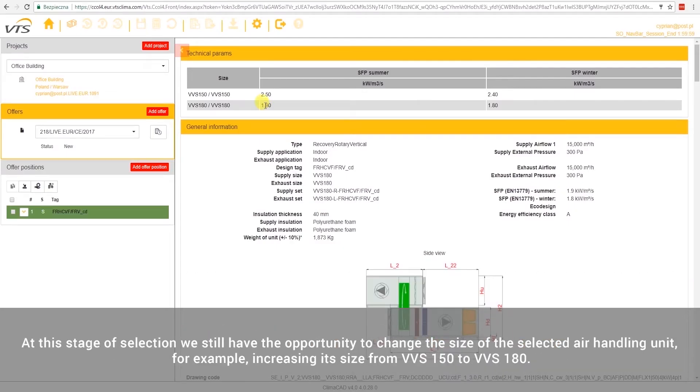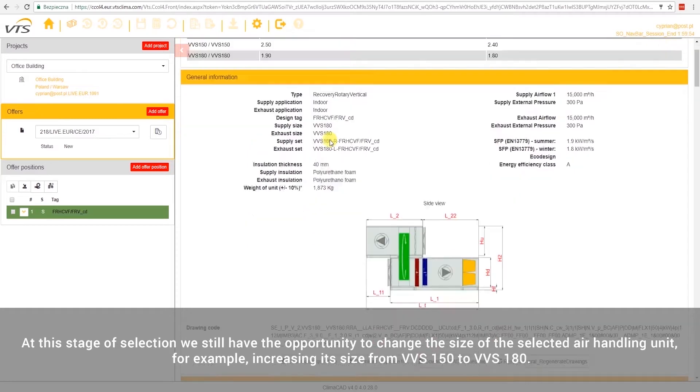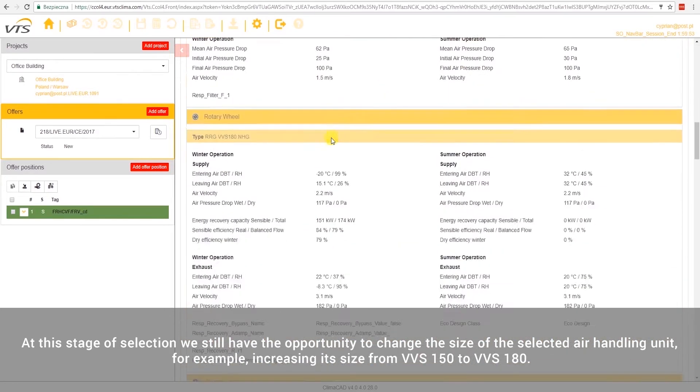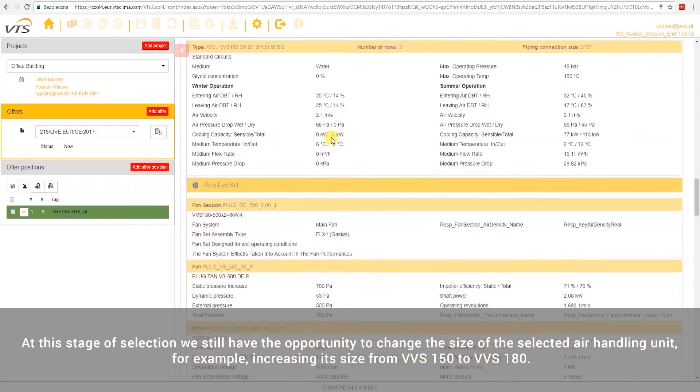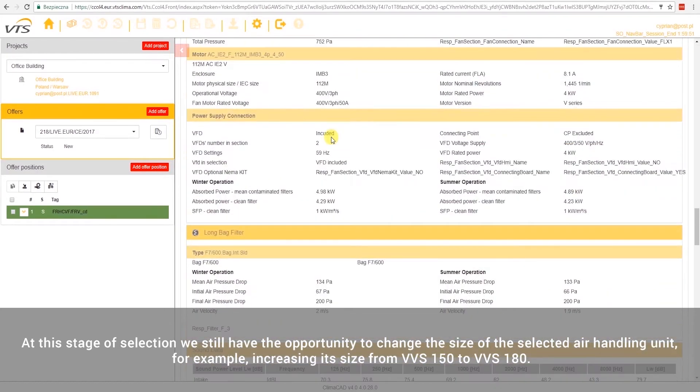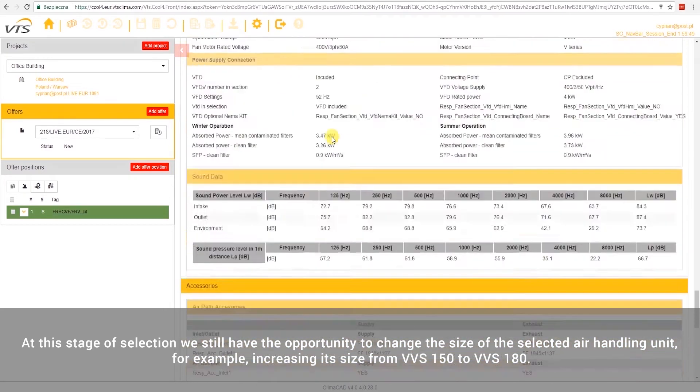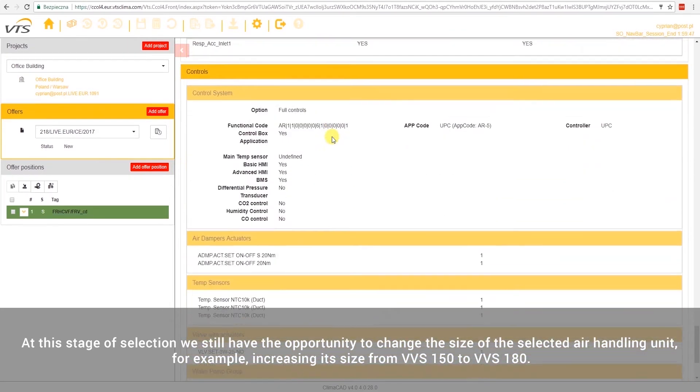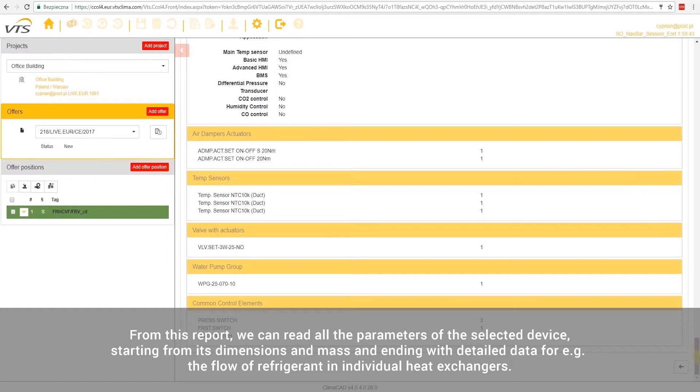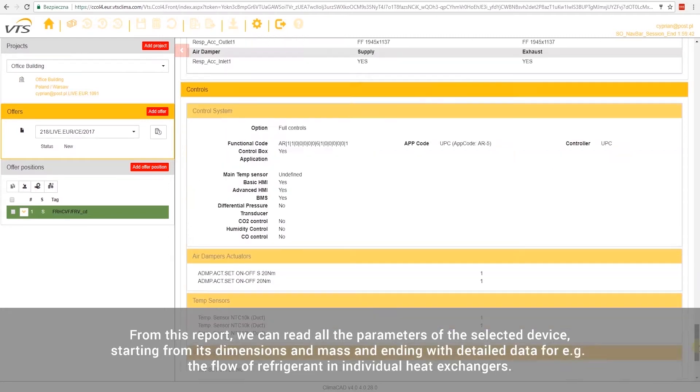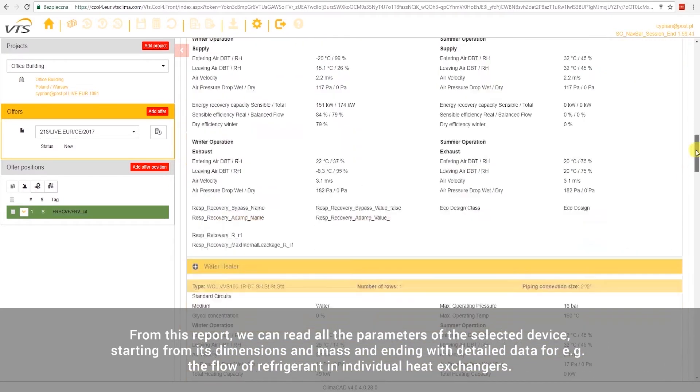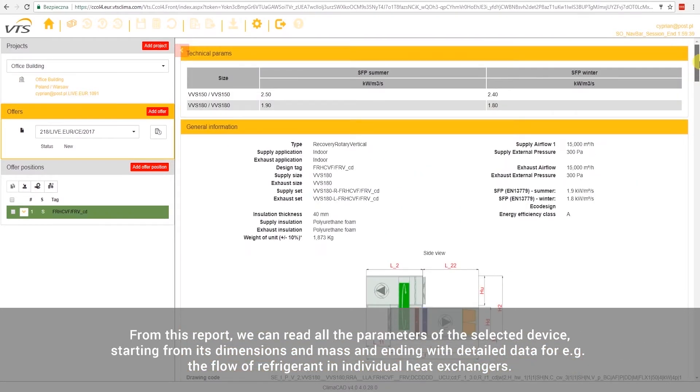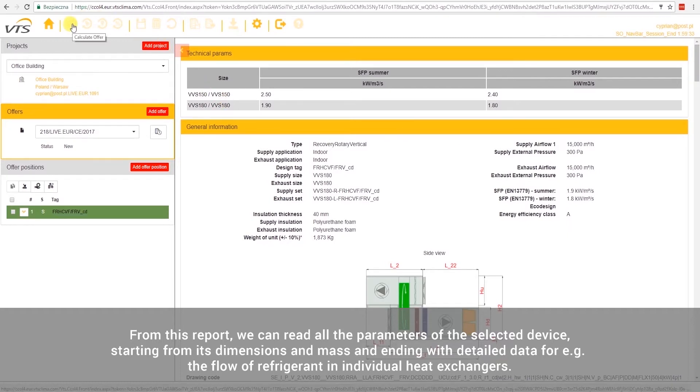At this stage of the selection, we still have the opportunity to change the size of the selected air handling unit, for example, increasing its size from VVS 150 to VVS 180. From this report, we can read all the parameters of the selected device, starting from its dimensions and mass, and ending with detailed data, for example, the flow of refrigerant in individual heat exchangers.